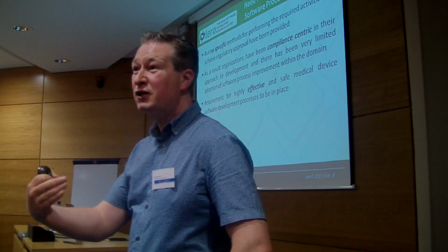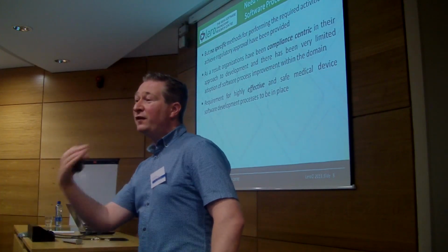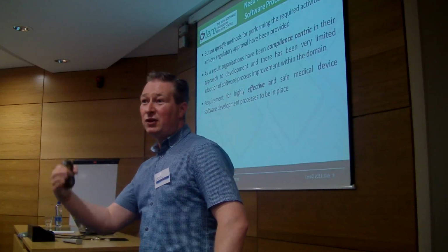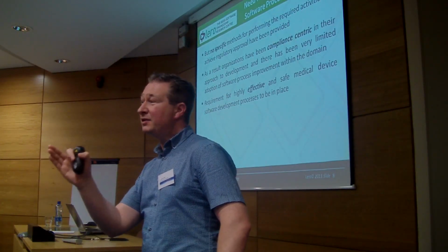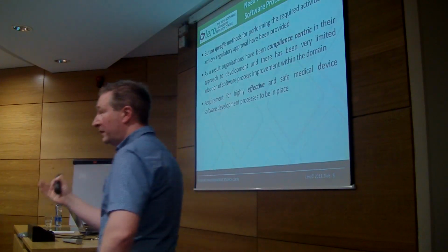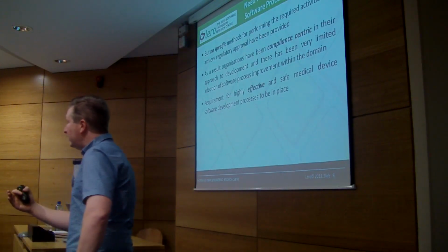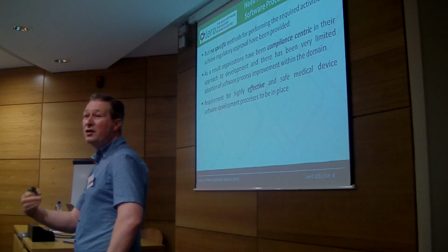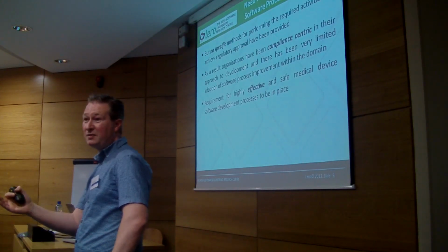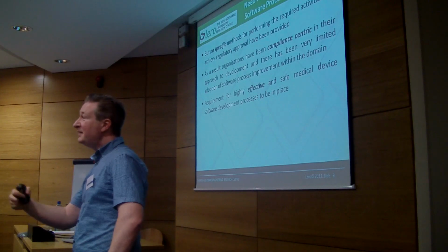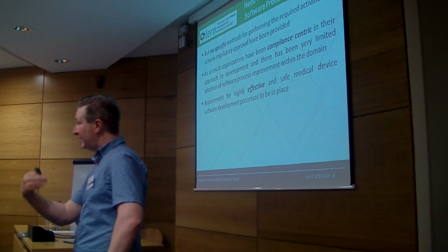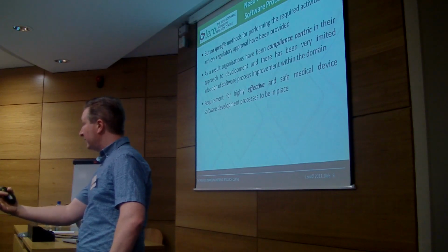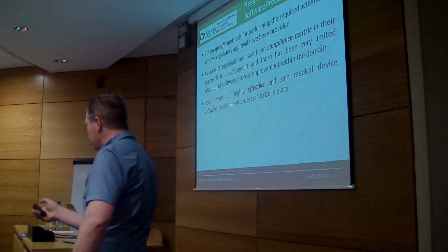your processes. First of all, you have defined, clear and well documented software processes to demonstrate what your template for developing the software will be. And secondly, you can actually provide objective evidence of how they have been followed. It's not enough just to define them, you also have to be able to stand over them, to say who implemented them, who the designated responsible people were that did something in a particular period of time. Where's your objective evidence?